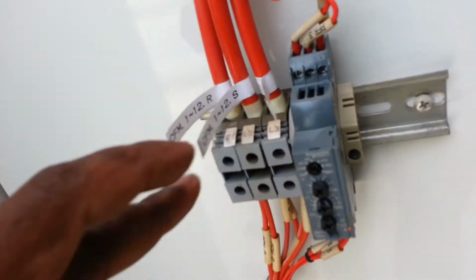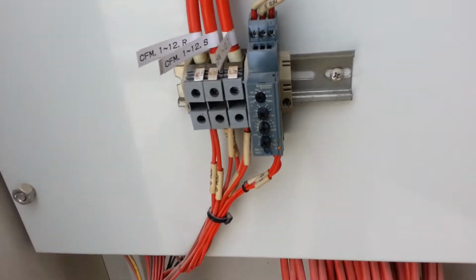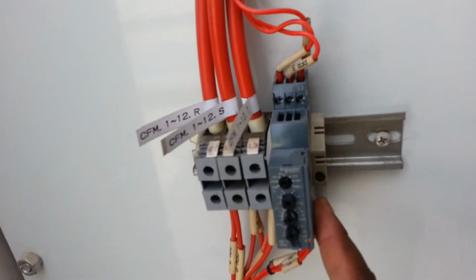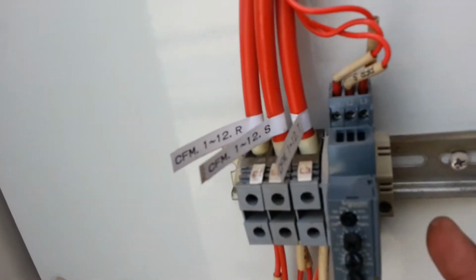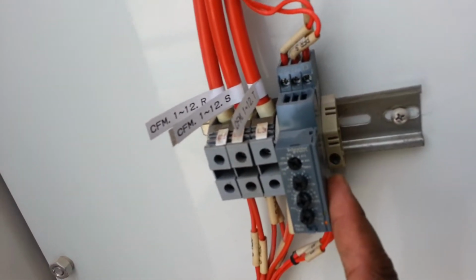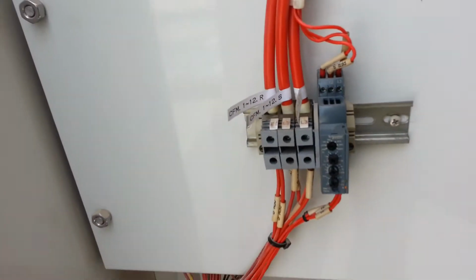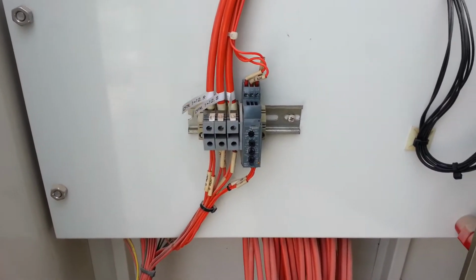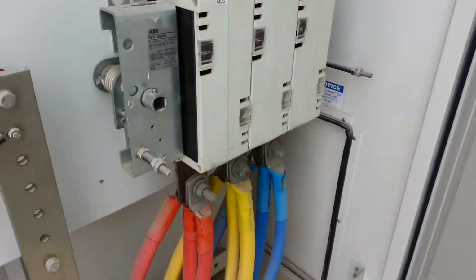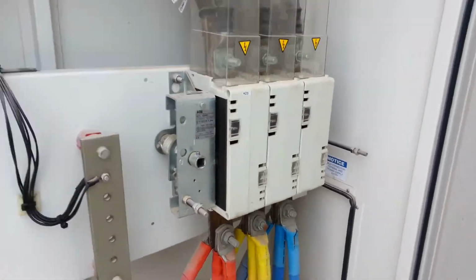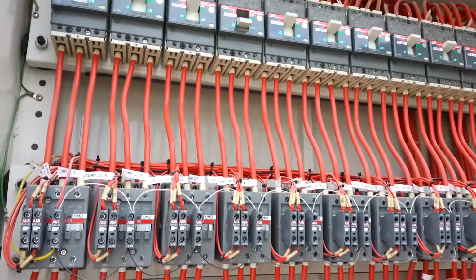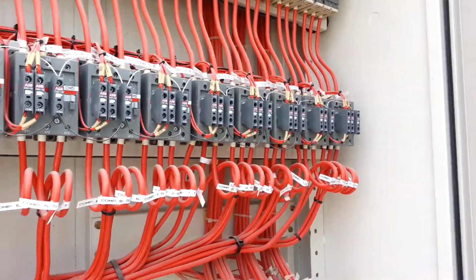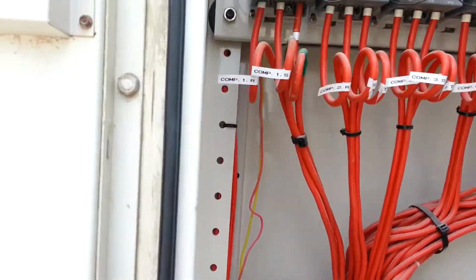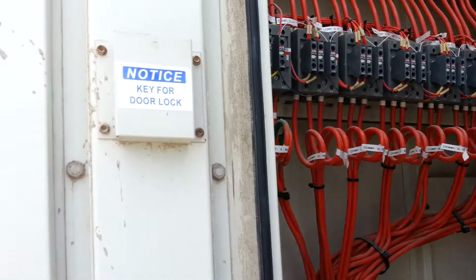This is the PFR, meaning power failure relay, and the phase sequence relay. If there is any problem in the phase sequence or any one of the phases fails, then the relay will turn off the main controller and the chiller will shut off. And this is the main incoming. And we have just looked at the main panel, control panel.